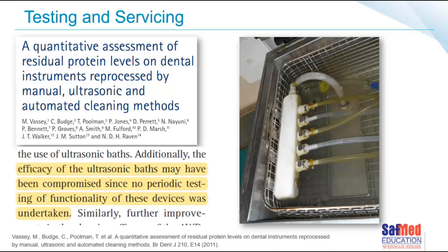Why would we get fungi in our ultrasonic cleaner? This is, of course, from leaving the water in overnight or over long periods of time, with no one checking the water. Remember, this could be because we were in a hurry, or it was change of shift. This is a manual ultrasonic cleaner, and if it's left overnight with the lid closed, there could be instruments in there, or no instruments, just dirty water and solution that's been stuck in there. The heat of the water condenses, and it's dark. It's the perfect, ideal breeding ground for some mold. 100%. And then when you drain the water at the end, you're draining that mold down into the tubing of the ultrasonic cleaner.